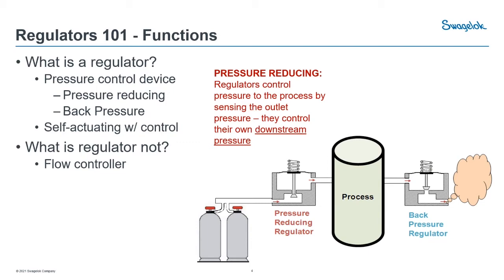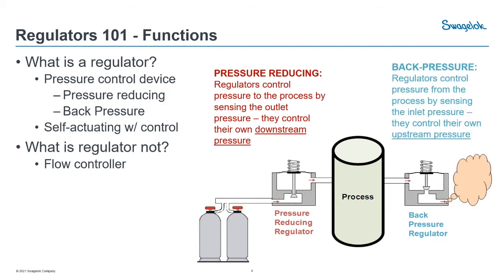It's very important to note that regulators are not flow controllers. These will get you to the pressure you need at a specific flow, but it is then your job to control that flow with something else, such as a needle valve or a restrictive orifice. A lot of people tend to pick these as flow controllers, but that's not what they're generally used for.